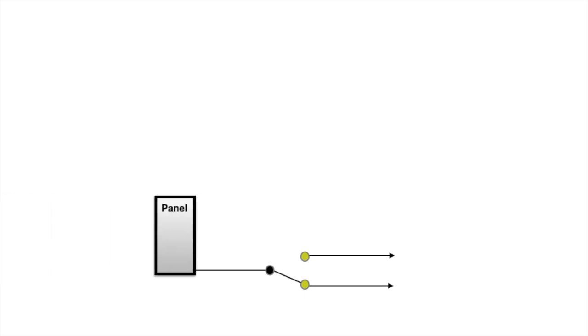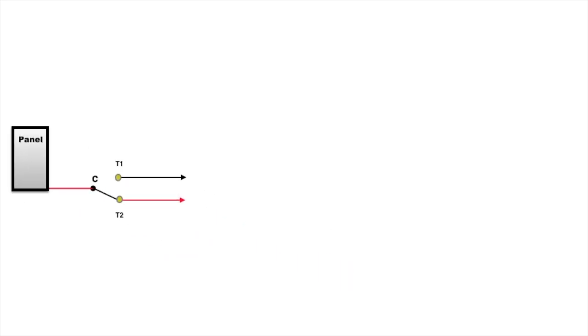The black contact is C. We call that common. And then the other two are called T1 and T2, and T stands for traveler. So as I operate the breaker, turn the thing on, you can see that traveler wire on the bottom is energized. The one on the top stays de-energized, because it's not made to the common contact. If I operate the switch, it'll just reverse the situation or the condition. Always one or the other, never both at the same time. That's what a three-way switch does.